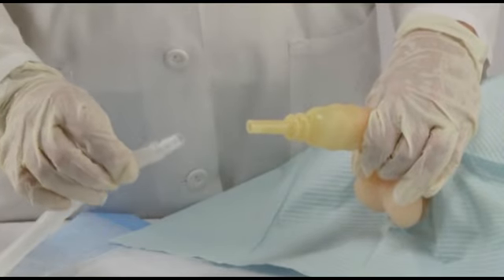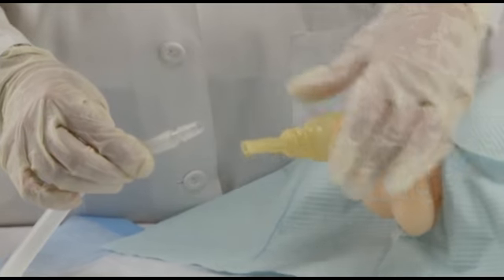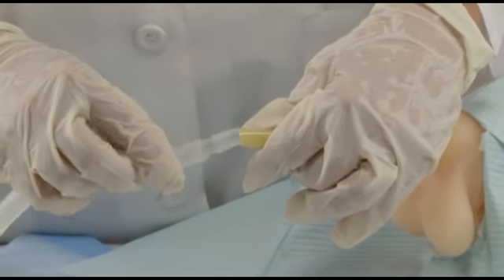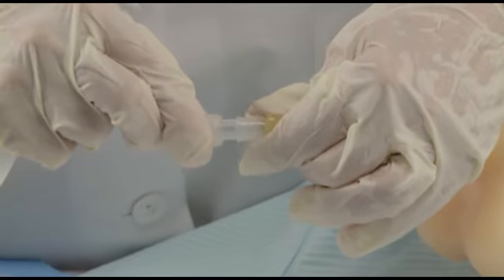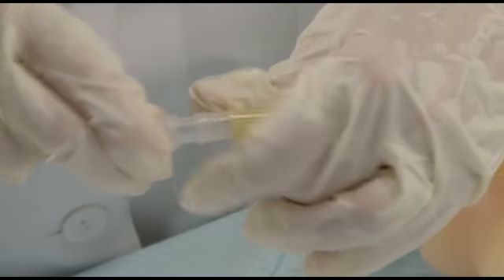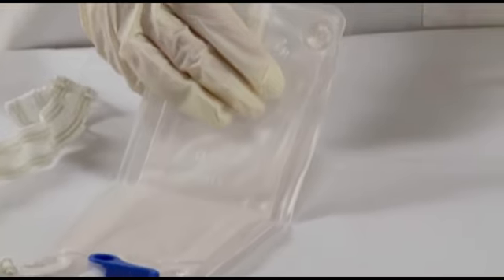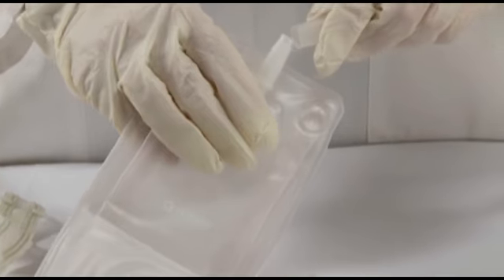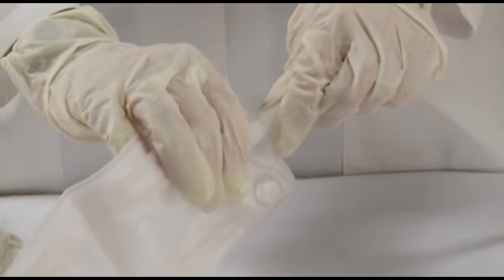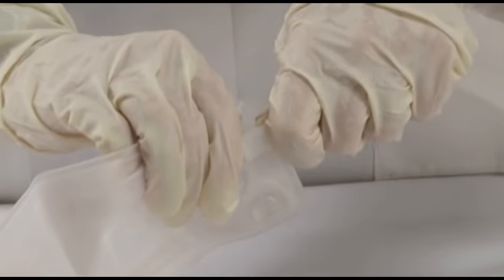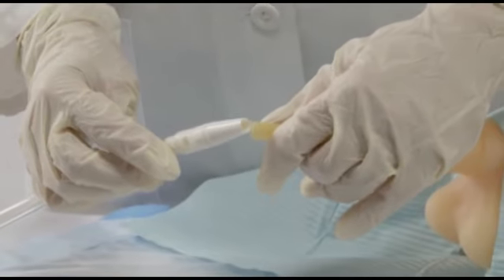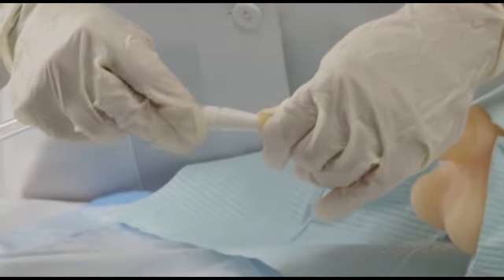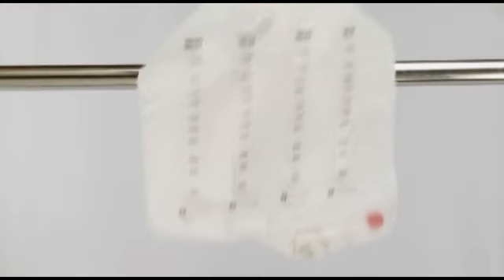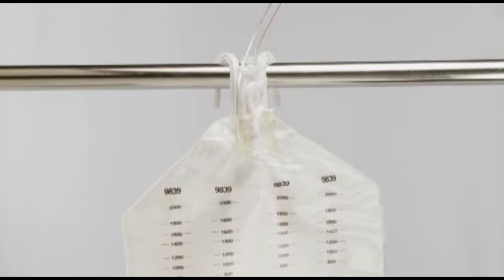Once the catheter is in place, you can connect it to either a urinary leg bag or other urine collection system. Simply push the extension tube connector into the tapered tip of the catheter to ensure a leak-proof seal. If you are using a Hollister urinary leg bag, connect the other end of the extension tube to the leg bag connector. Then position the leg bag on the patient's leg. If you're using a Hollister bedside drainage collection system, connect the extension tube. Then position the bedside collector to the patient's bed. Make sure the bedside collector is lower than the patient so that gravity allows urine to drain into the collector.